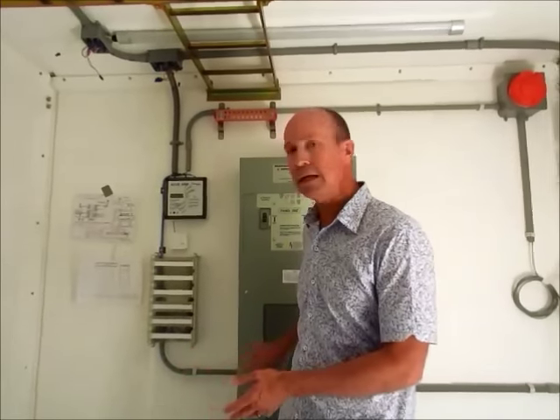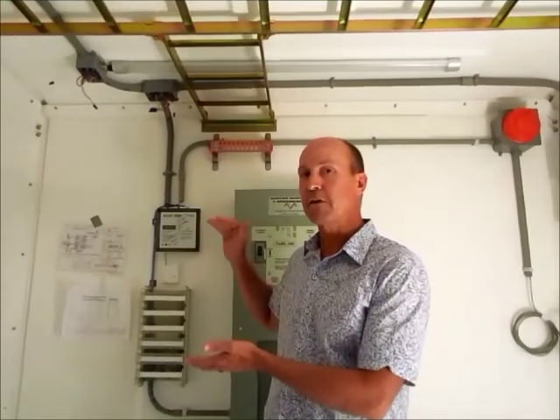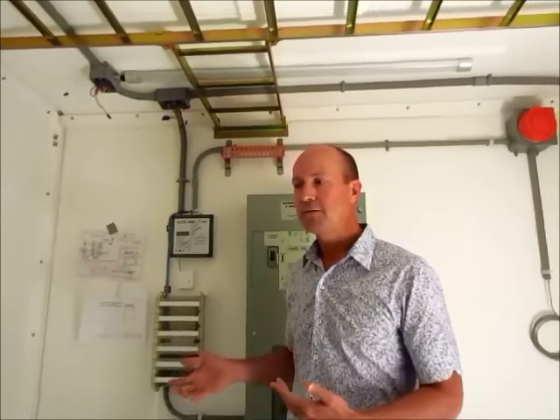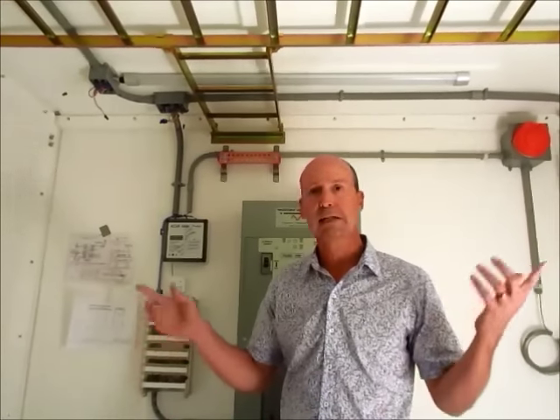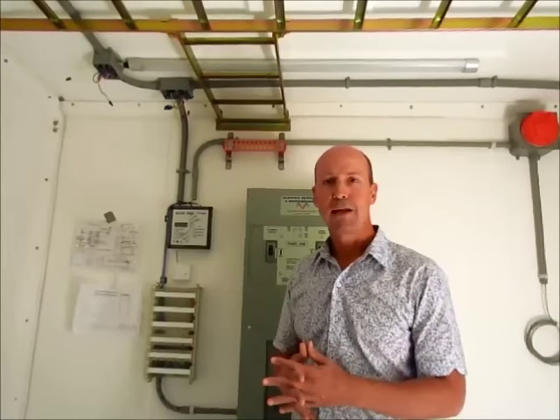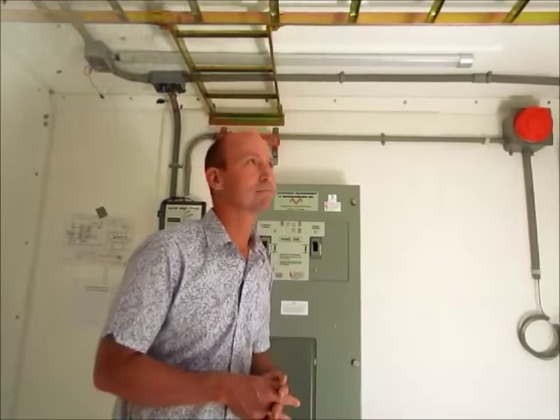So the power comes in as AC power, it's transferred via a rectifier down to 48 volt DC power, and then if there ever is a glitch in the grid, there's never a glitch inside the enclosure. The lights still work, the fans still work, all the equipment still works, and you have uninterrupted telecommunications service.